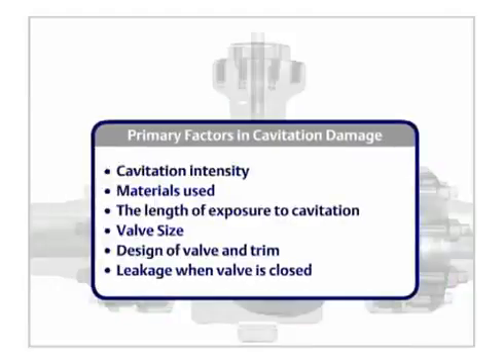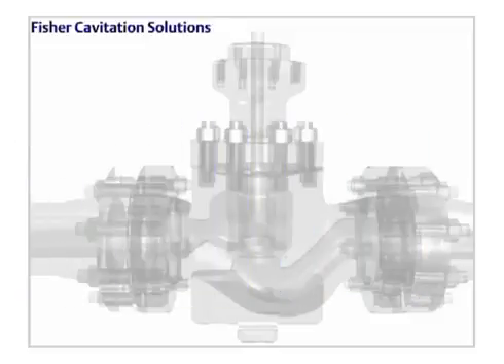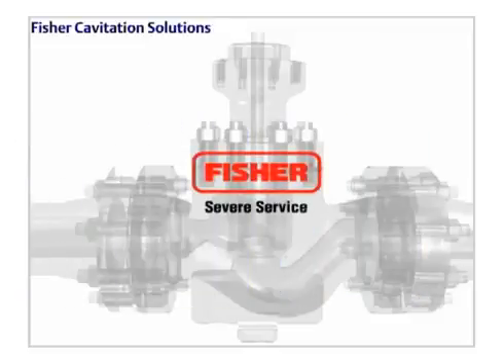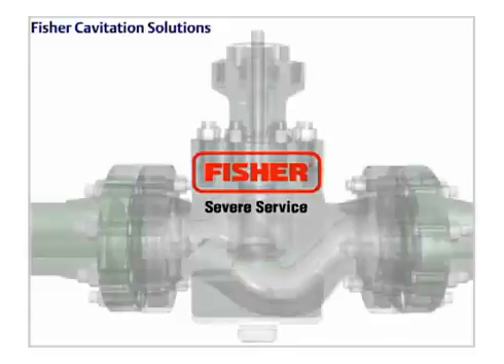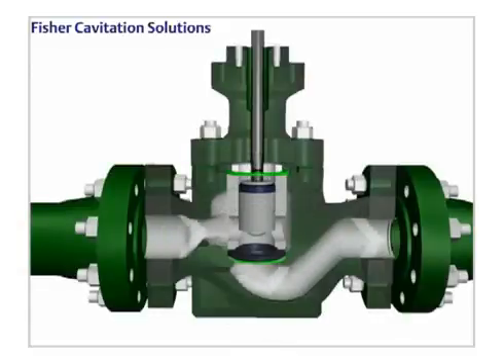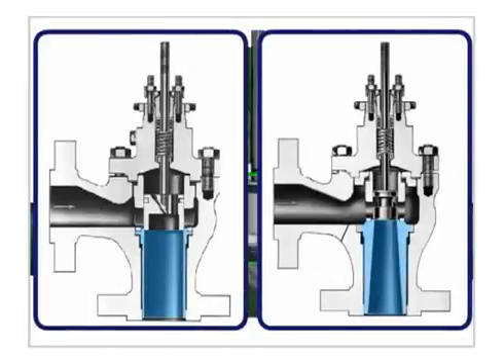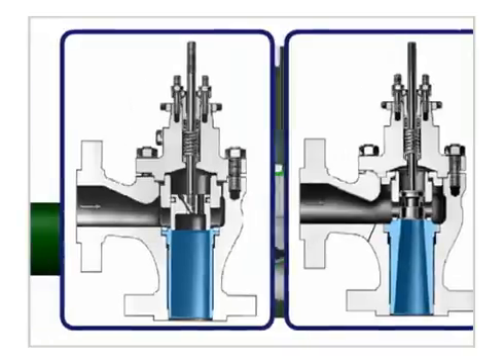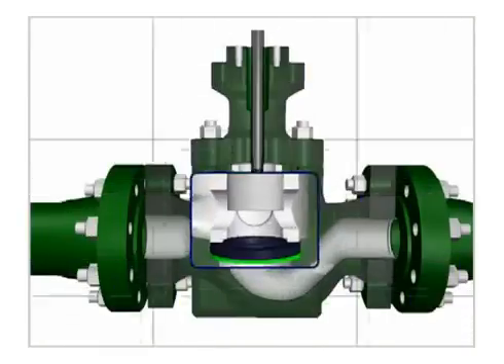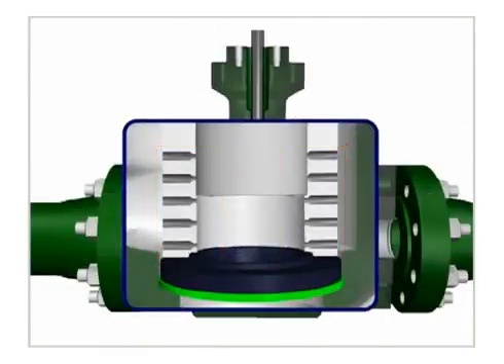Cavitation damage can be reduced by altering or accommodating any of these factors. Cavitation damage can often be reduced or prevented by using the proper components. Emerson offers these solutions. Valve liners are constructed of hardened materials to protect the valve body. Pressure staging keeps the pressure from falling to near a liquid's vapor pressure, which helps prevent vapor bubbles from forming.